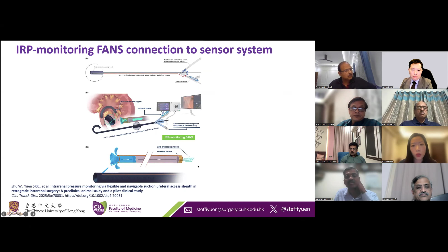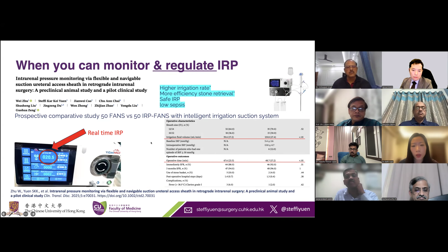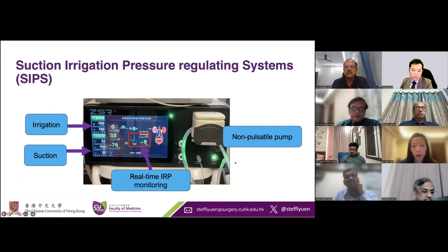One of the sheaths conducts the pressure through air instead of liquid, so you need to know which kind of IRP monitoring fans you're looking into. But in essence, when you can monitor and regulate the pressure, we can use a higher irrigation rate, which results in more effective stone retrieval. And because IRP is regulated, it's within safe limits with a very low sepsis rate, from this pilot comparative study of 50 non-IRP monitored and 50 monitored FANS with the integrated suction irrigation. A closer look at irrigation parameters, suction parameters, and real-time intrarenal pressure monitoring and a non-pulsatile pump.